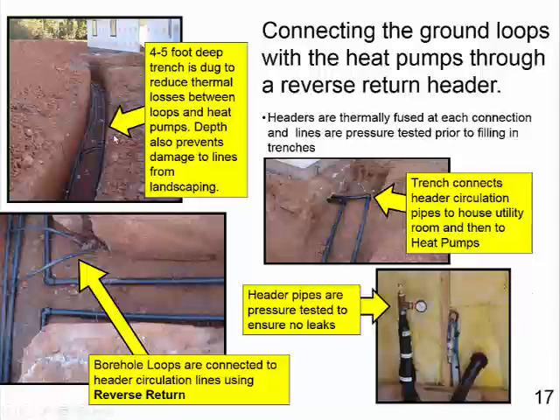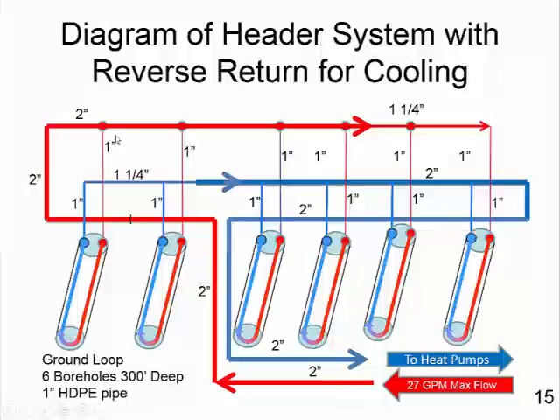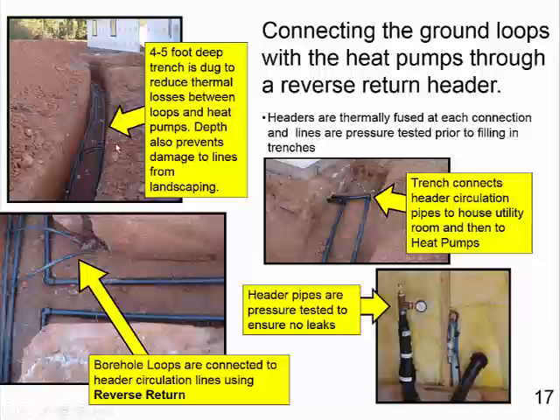You notice there are 3 pipes in the ground here, and that's caused by the way the reverse return is set up. I'll just go back to that. You see there are 3 different pipes here, and that's what you see in the trench, the 3 pipes. Here you see one pipe hooked onto another pipe, so it's not a continuous flow from one to the other. And that's the reverse return.